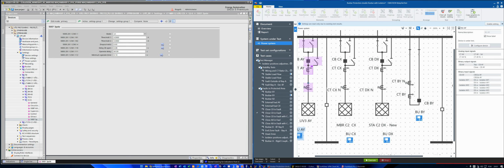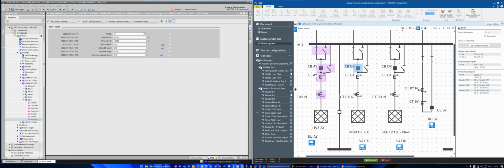So for example, if maintenance forgot the grounding on this pole of the circuit breaker, I have a fault here. And if my circuit breaker is open, I am in this case, with a fault here, between the CTs and my circuit breaker.